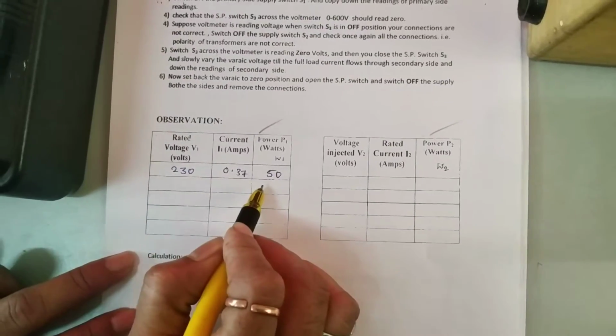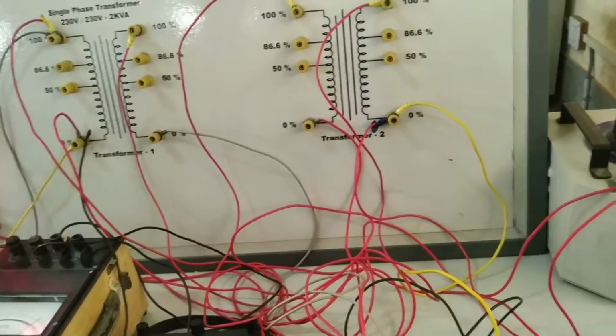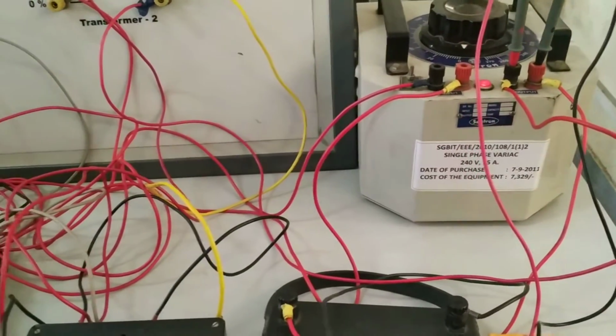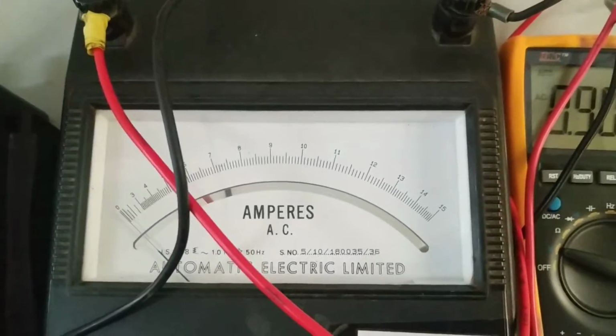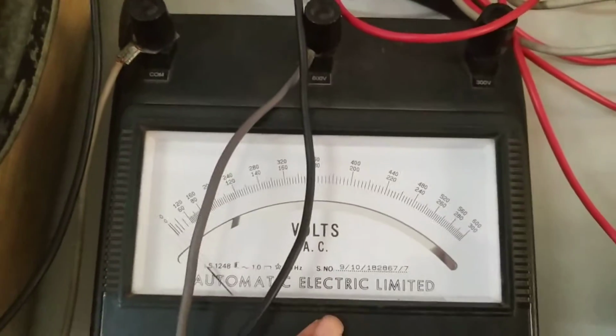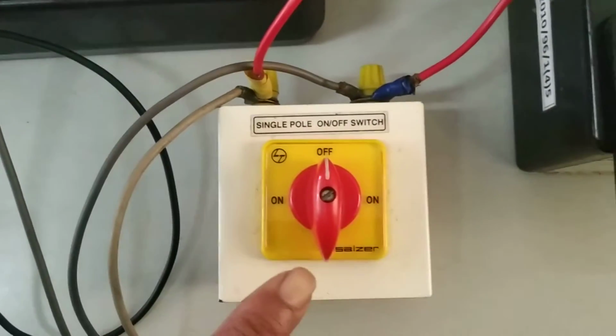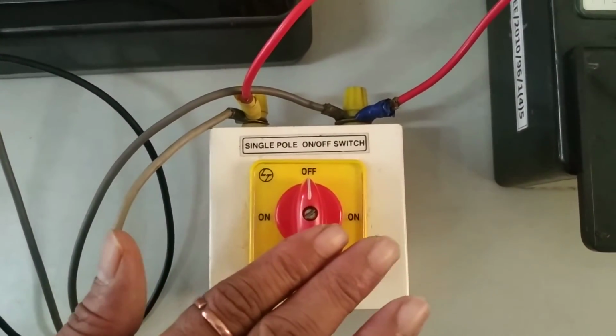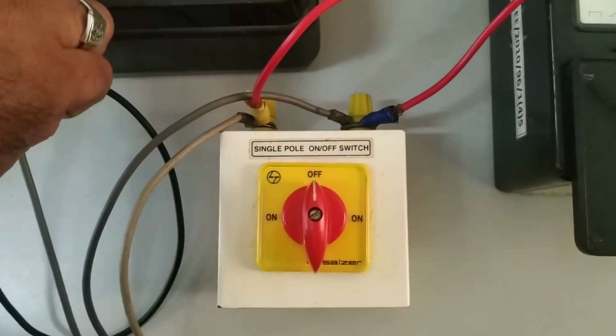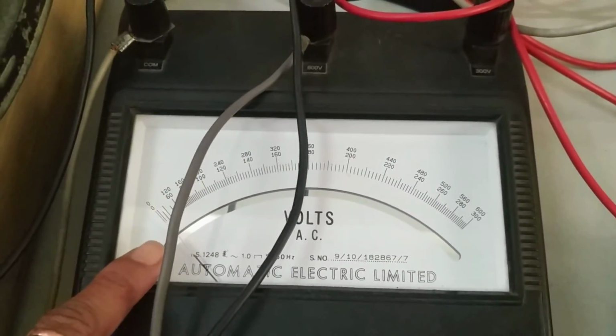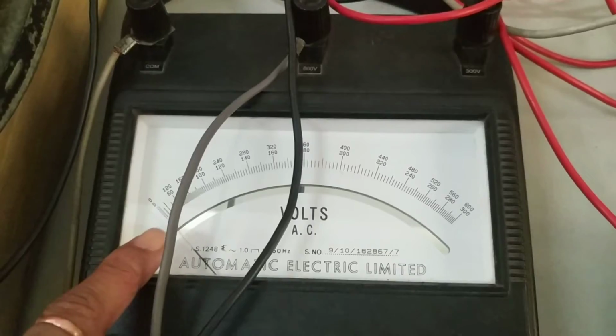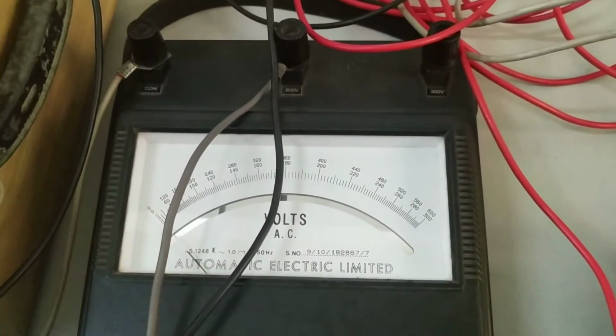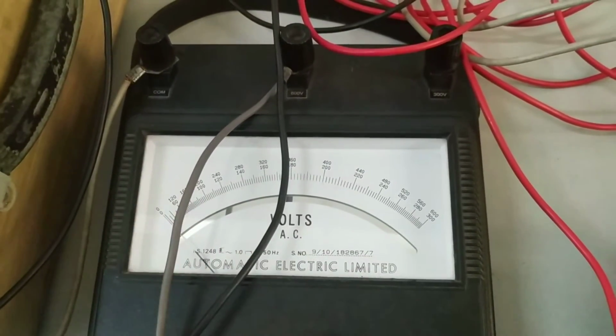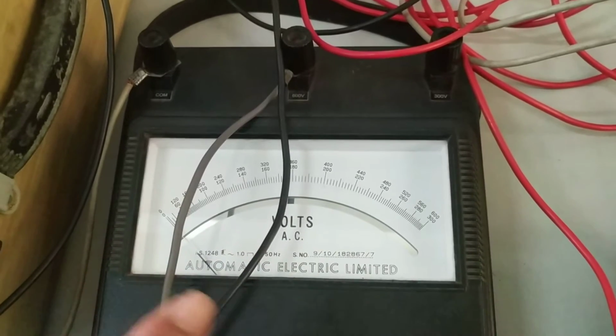So we need to take one set of readings first, and after that, with the help of the other autotransformer, we need to apply a reduced amount of voltage to get the rated current in the ammeter. Before that we need to check the value in the voltmeter which is connected across this switch. We are using one switch here. This should be at the off position initially, and after that we need to connect one voltmeter across this switch. If the voltmeter across the switch is showing 0, no problem, we can continue the experiment. If it is not showing 0, sometimes it may show 230 plus 230, that is 460 volt.